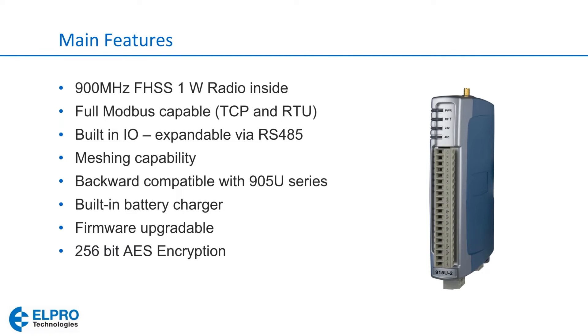The 915U2 has full Modbus capability, so it can act as the Modbus RTU master or slave, and it can also do Ethernet Modbus — Modbus TCP — by acting as the Modbus server or the Modbus client. It has built-in I/O that we're going to talk about in just a few minutes, and if this I/O is not enough, it can be expanded via RS-485.